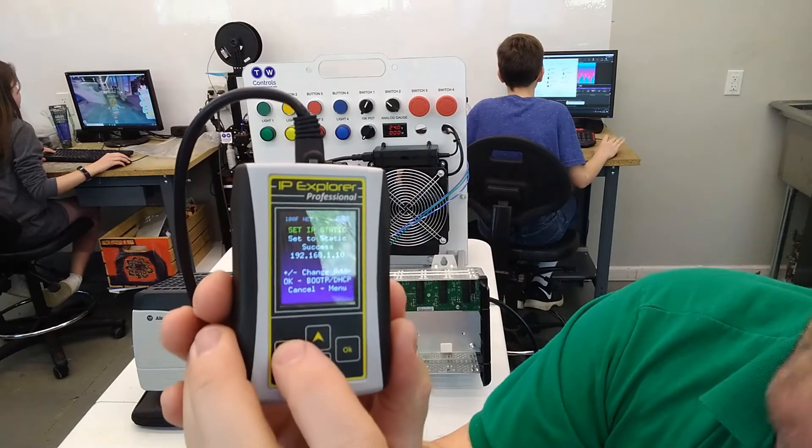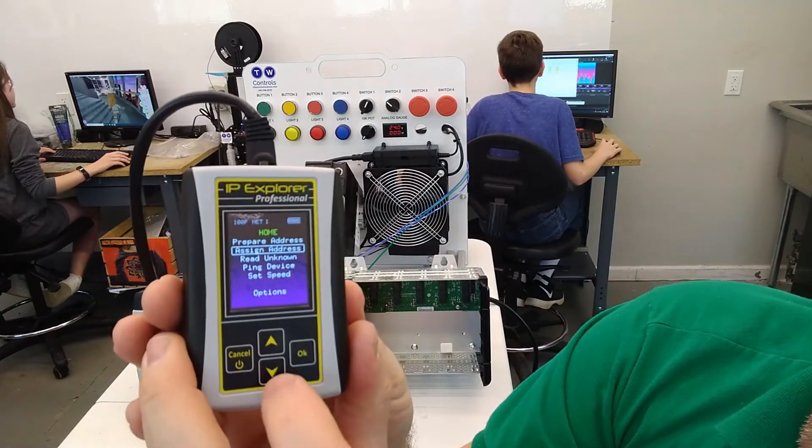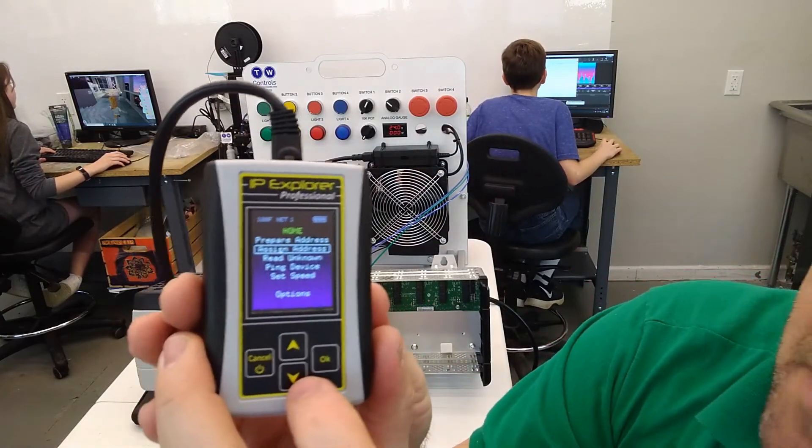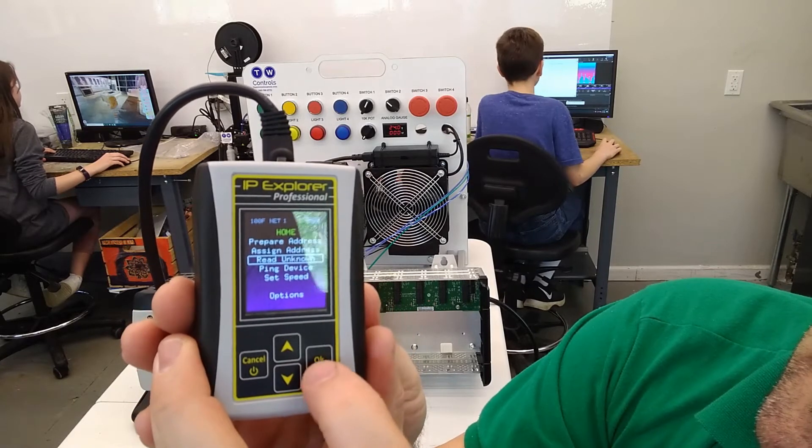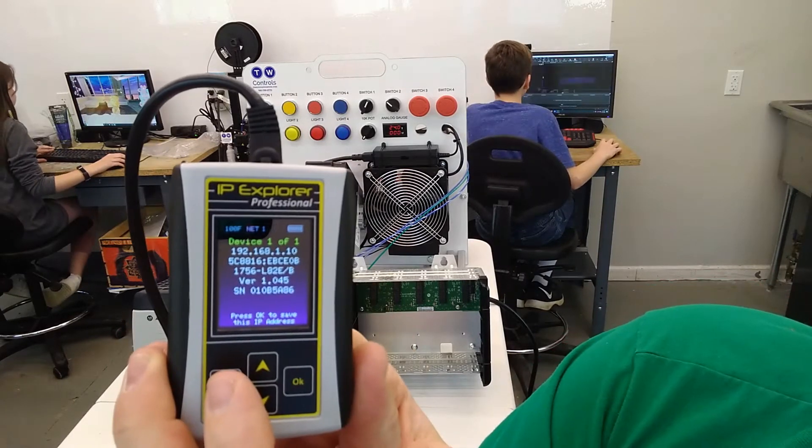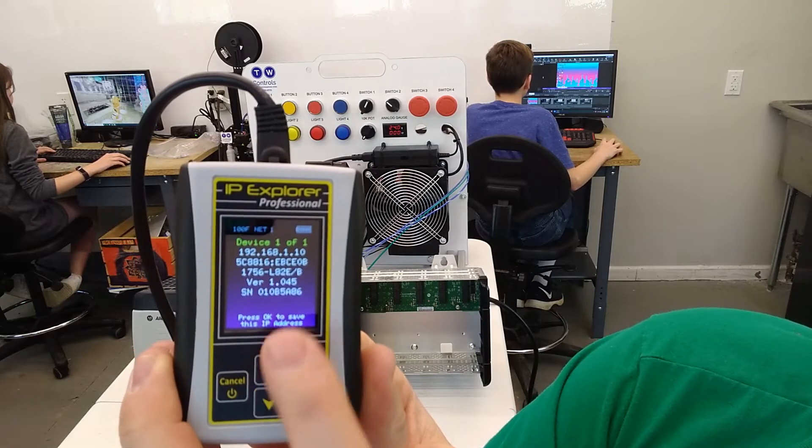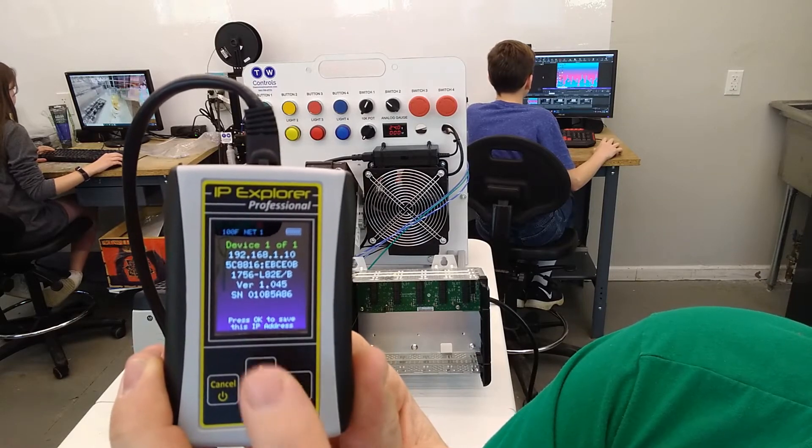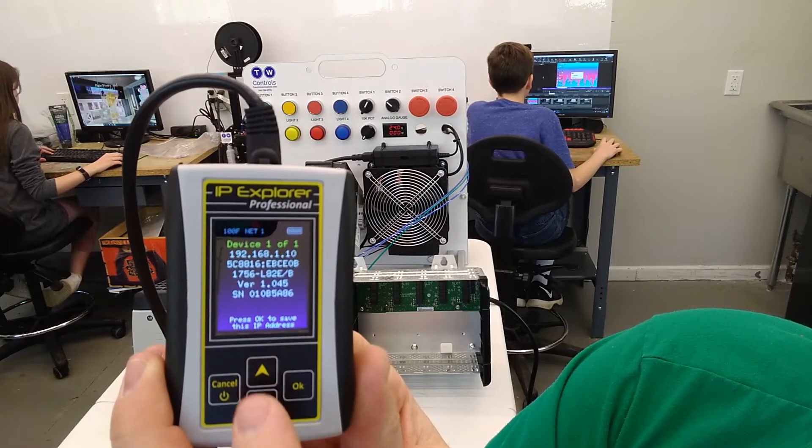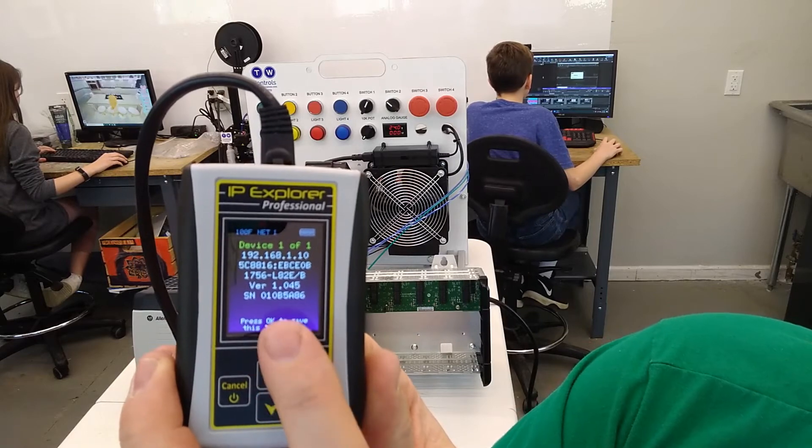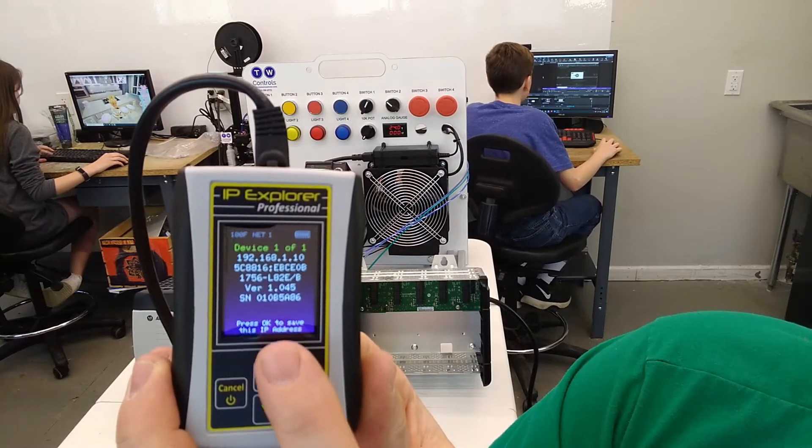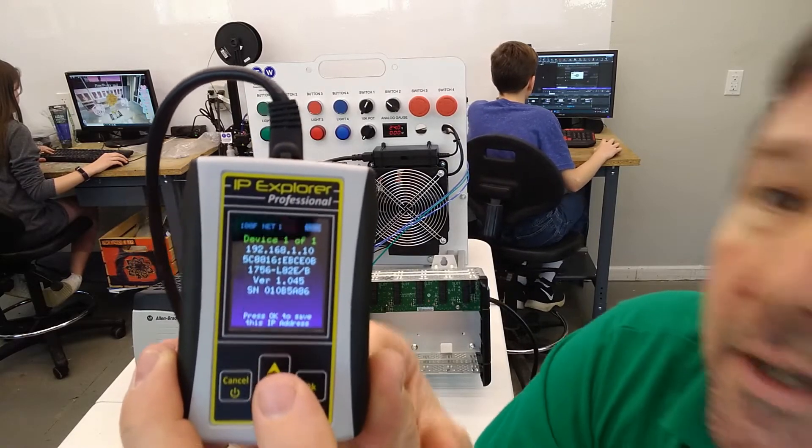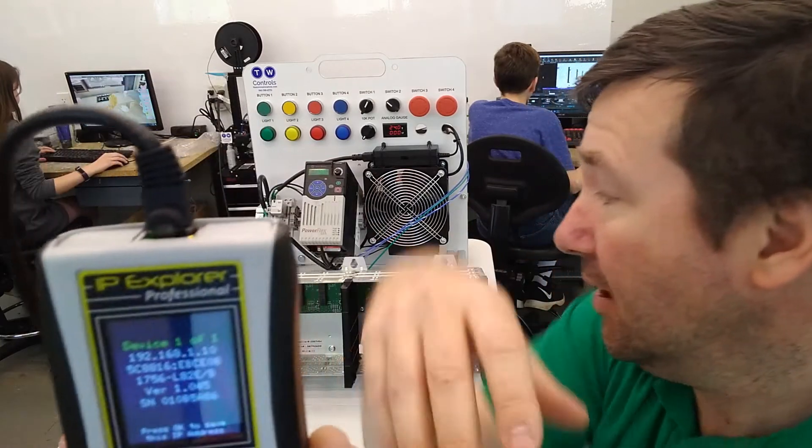We need to back out of this, and we can read it and verify it. So I'm going to go to read unknown IP, and it says 192.168.1.10. It also gives the MAC address, the actual processor part number, and tells us right now we're at version 1.045, and gives us a serial number.